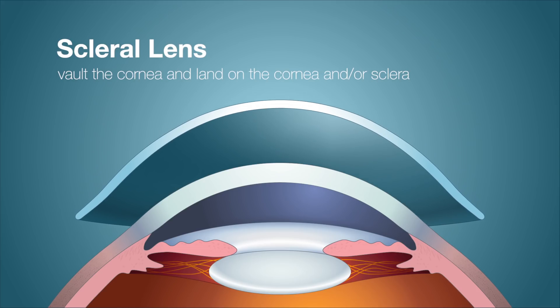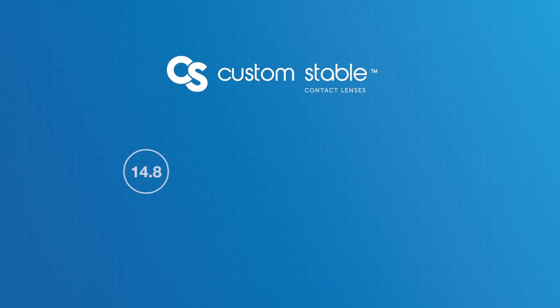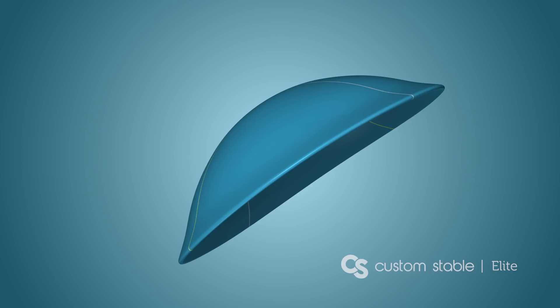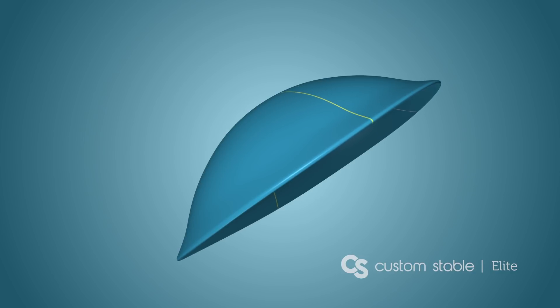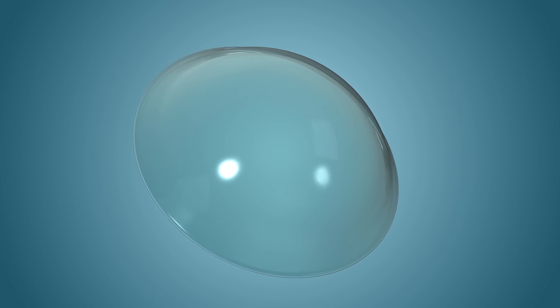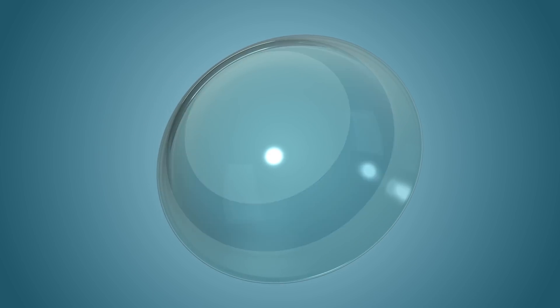The Custom Stable is a scleral lens design. Scleral lenses, unlike traditional corneal GP lenses, vault over the cornea and bear their weight on the cornea and/or sclera. The Custom Stable is available in 14.8, 15.8, 16.8, and 17.8 mm sizes, and can be ordered with a standard spherical back surface or upgraded to the Custom Stable Elite, which has a toric landing zone that customizes the lens to a toric sclera. The Custom Stable lens has three sections called zones: the central visual zone, the limbal clearance zone, and the scleral landing zone.